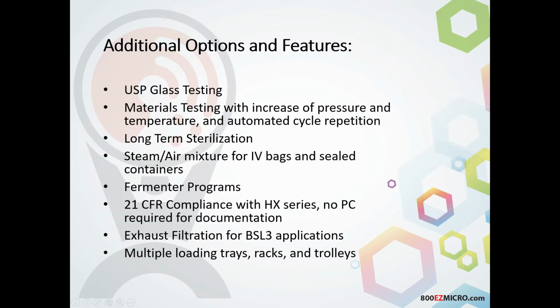So additional options and features that we have: we do offer USP glass testing, a very specific glass test parameter where we have complete control over the process, so we can actually achieve that USP glass testing, which is a very specific programming system. Materials testing with the increase of pressure and temperature, and automated cycle repetition. So we can change sterilization up to days, and we can run multiple cycles as well. So we can run this up to 99 days per cycle, and also have that repeat, I think 99 times as well. So in essence, you can hit start and sterilize for years.